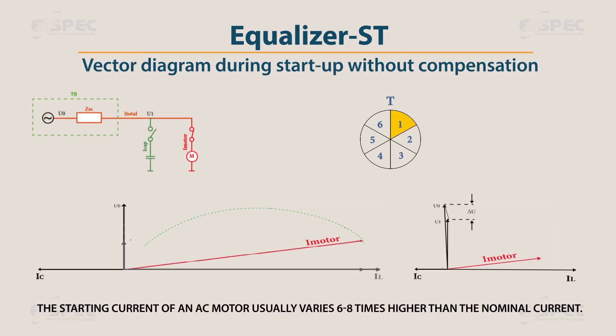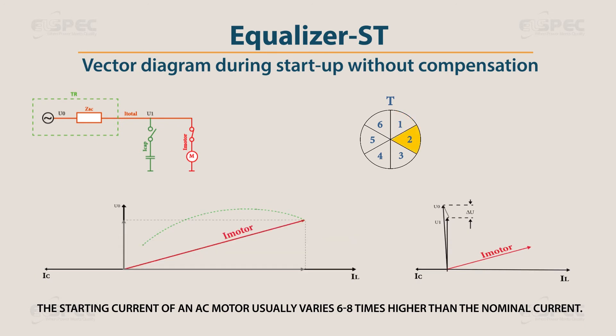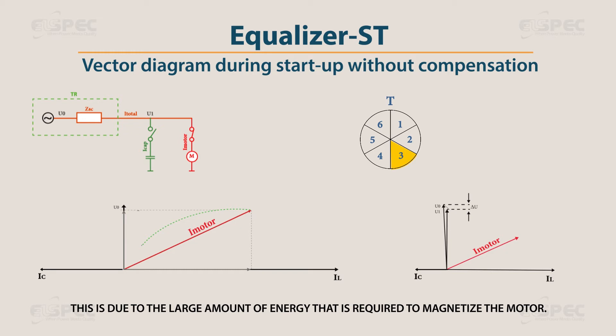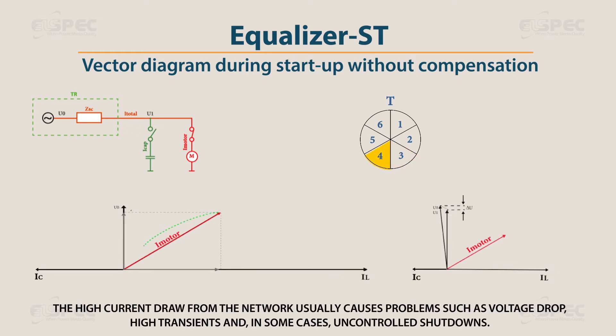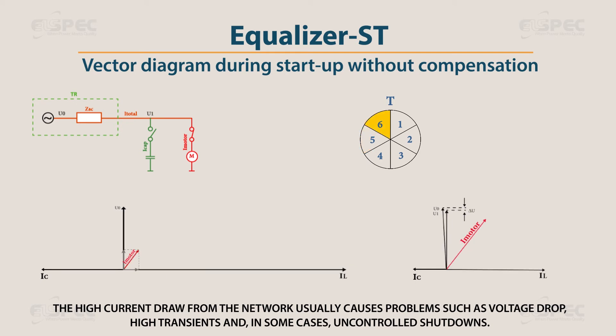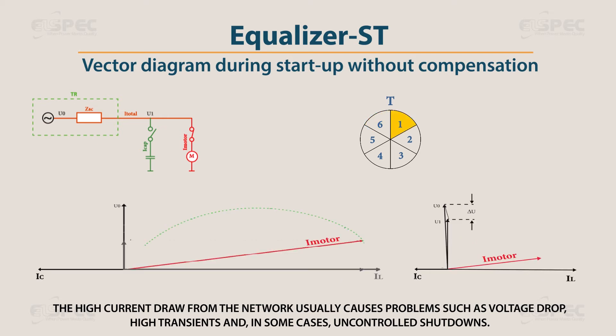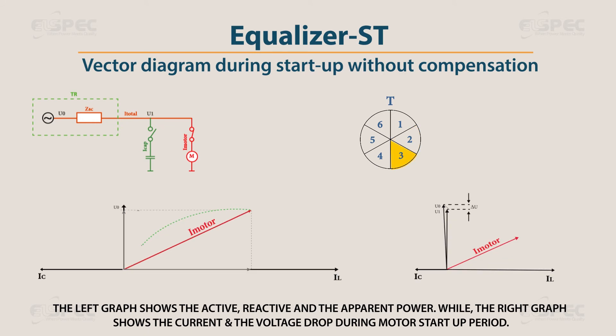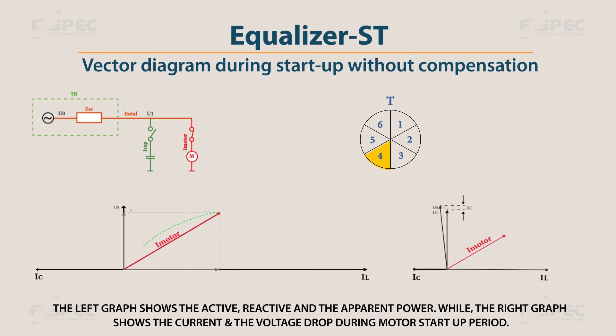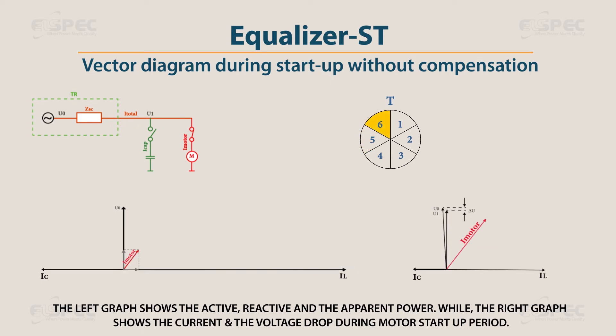The starting current of an AC motor usually varies 6 to 8 times higher than the nominal current, due to the large amount of energy required to magnetize the motor. The high current draw from the network usually causes problems such as voltage drop, high transients, and in some cases, uncontrolled shutdowns. The left graph shows the active, reactive, and apparent power, while the right graph shows the current and voltage drop during the motor startup period.